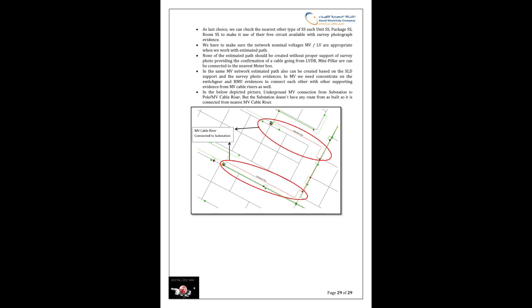In the same MV network, an estimated path can also be created based on SLD support and survey photo evidence. In MV, we need to concentrate on the switchgear and RMU evidence to connect each other, with other supporting evidence from MV cable risers as well. In the picture below, an underground MV connection from substation to pole MV cable riser: the substation doesn't have any route from as-built, so it is connected from the nearest MV cable riser.